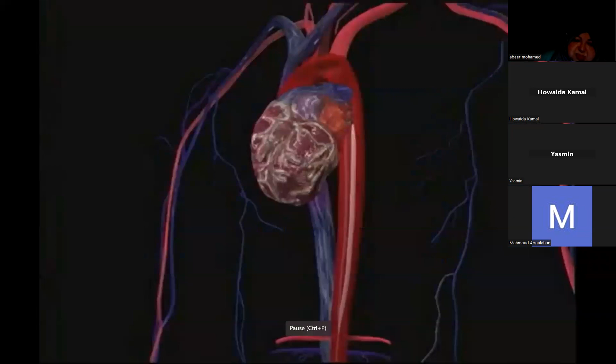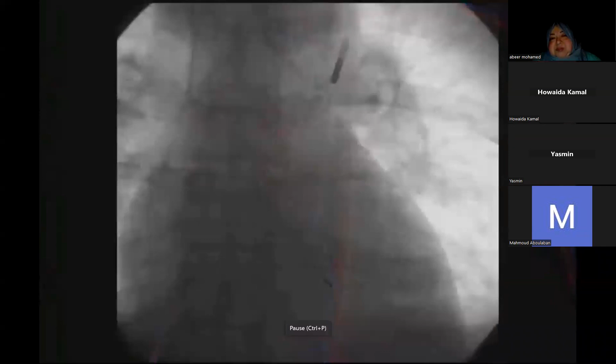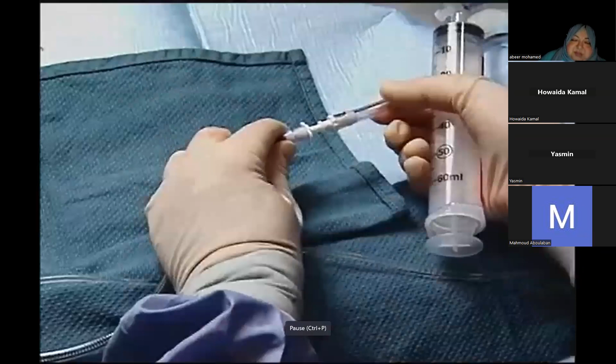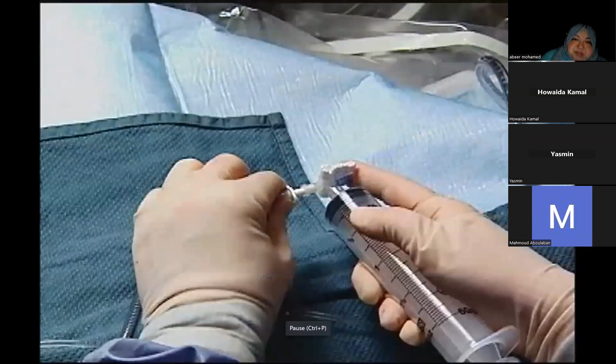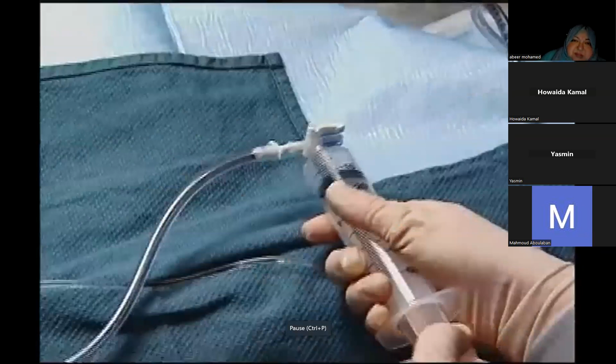Sometimes the balloon membrane may not completely unfold as pumping begins. If fluoroscopy is in use, observe for uniform inflation of the balloon membrane. If you suspect the balloon has not completely unfolded, detach the balloon catheter from the extender and attach a 3-way stopcock and a 60 cc syringe to the male luer fitting of the balloon catheter. Aspirate to be sure no blood is returned through the catheter tubing. Inflate and deflate the balloon by hand with 60 cc's of air or helium.